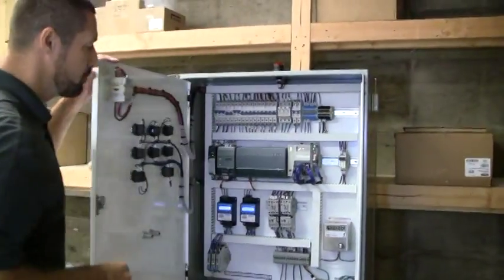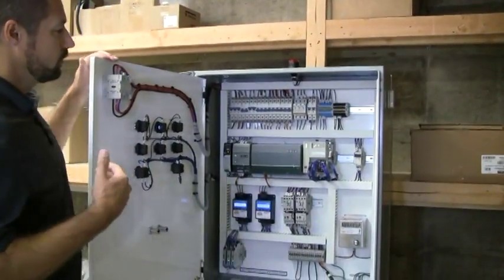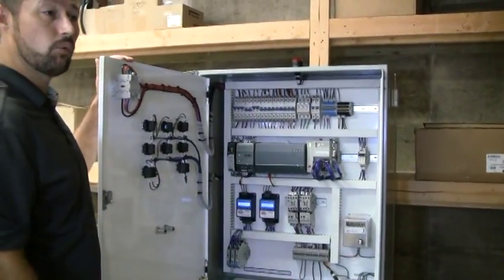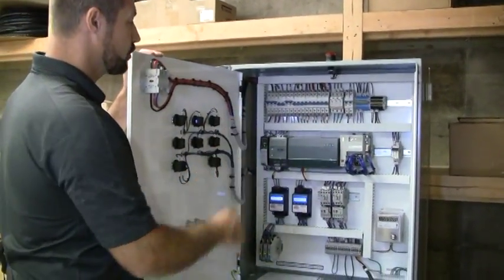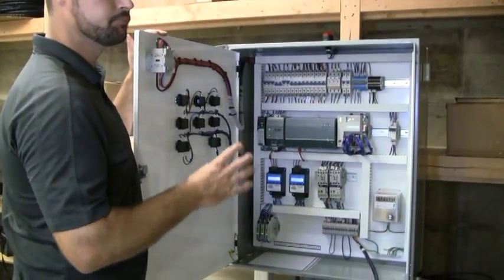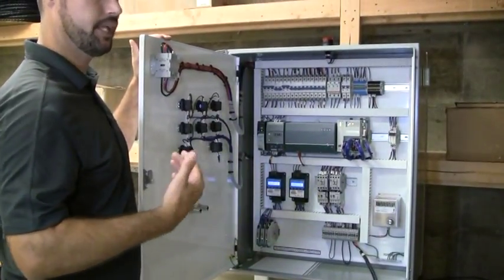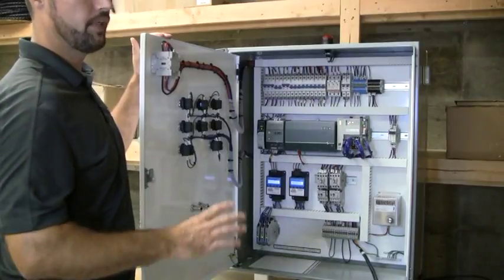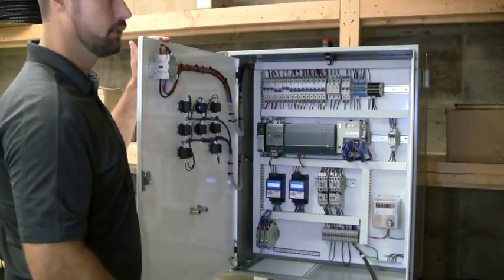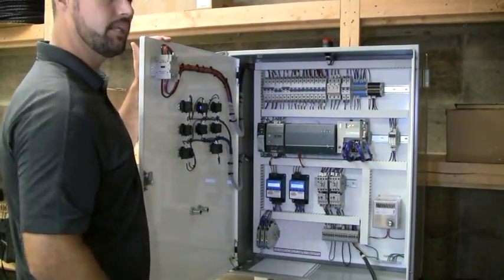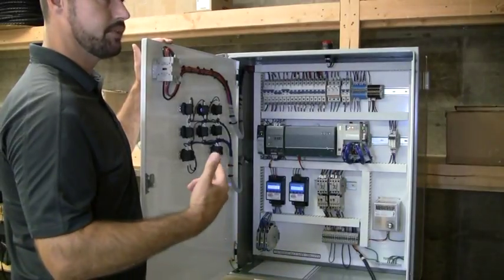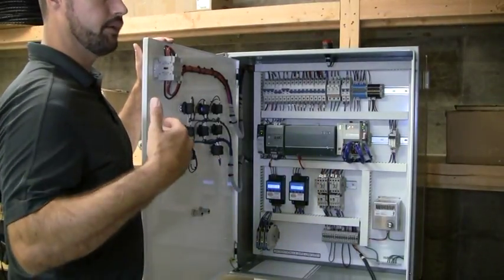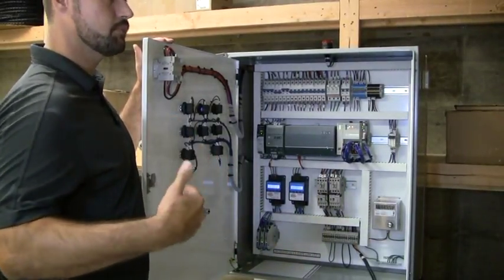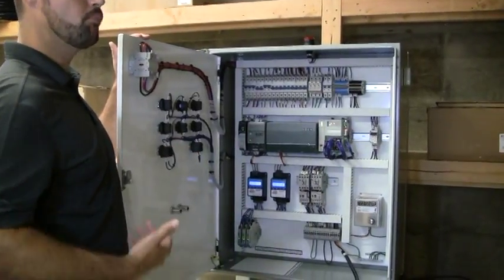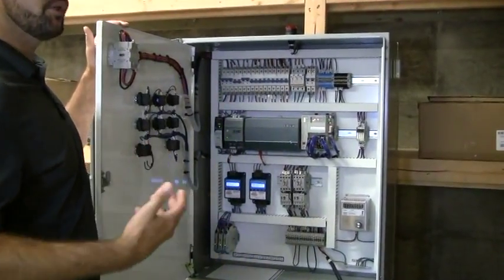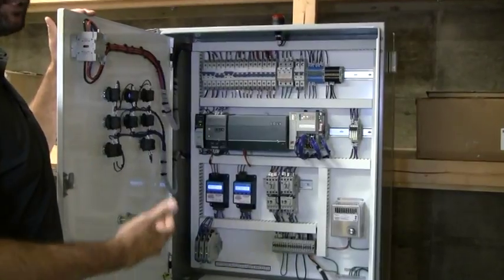On the inside is where all the main brains come into play. So again, Allen Bradley, Rockwell. We're using their controllers, a CompactLogix series controller. These controllers are able to integrate with SCADA systems very easily. That's their design, that's their intent. So everything is Ethernet connection. We can integrate cellular modems, we can integrate other systems that can bring mobile information so that people aren't having to go out and check it continually.